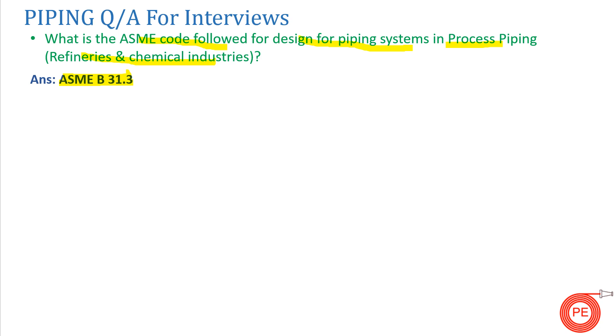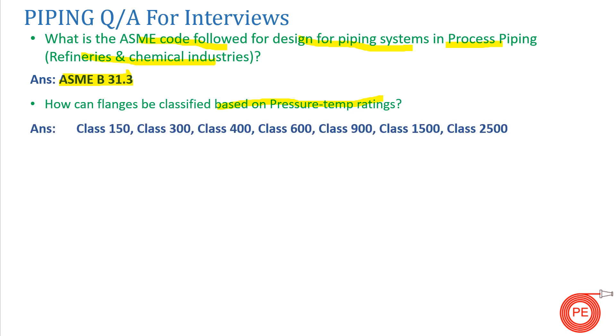How can flanges be classified based on pressure-temperature rating? When purchasing a flange, we determine its pressure-temperature rating to select it for a particular service and operation. Flanges are generally available from Class 150 to Class 2500, covering Class 300, 400, 600, 900, and 1500. The classes vary according to pressure, temperature, and material — if pressure or temperature changes, the pressure-temperature rating also changes.